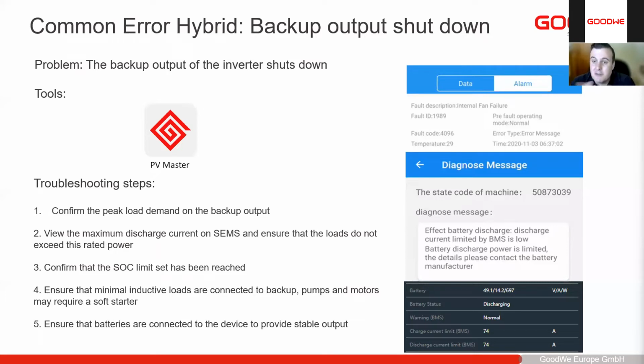And then we always need to make sure there are batteries connected to the device if we are using the backup output of the inverter. If there aren't any batteries and we just have solar, the backup might stay on, but as soon as there's a load change, the backup shuts off.